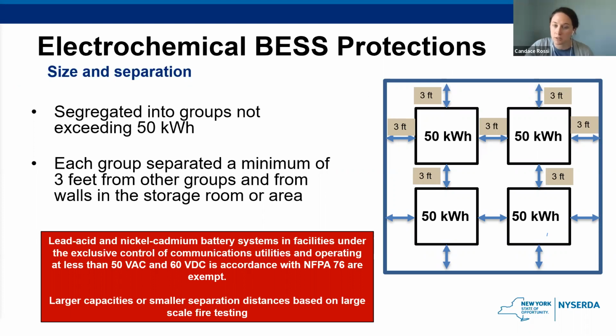There are two exceptions to this requirement. One is for communication utilities, and one is based on that large-scale fire testing. So as we spoke about earlier, this is one of the requirements that based on large-scale fire testing, there will not be propagation of fire or any other hazards. This requirement can be changed per the fire code official. And I will say that often for walk-in units, smaller separation distances are allowed based on the result of large-scale fire testing. But once again, this will have to be something that the applicant shows you and that the fire code official approves.